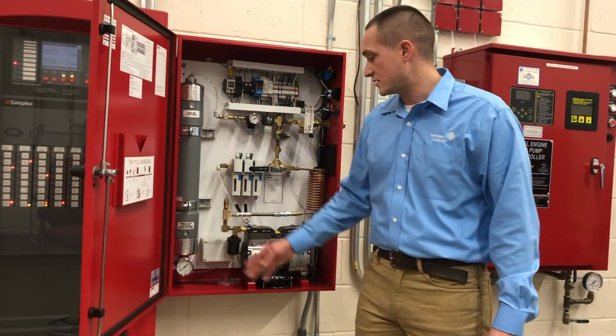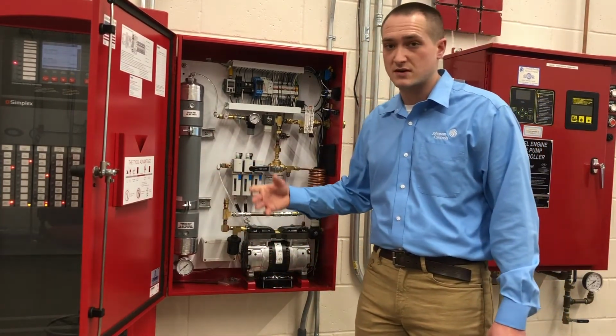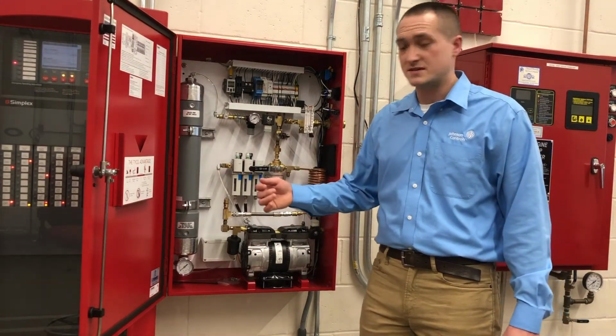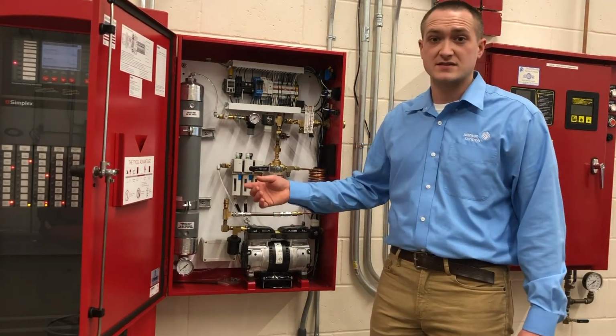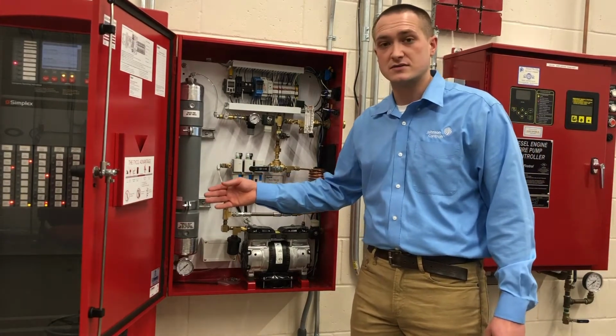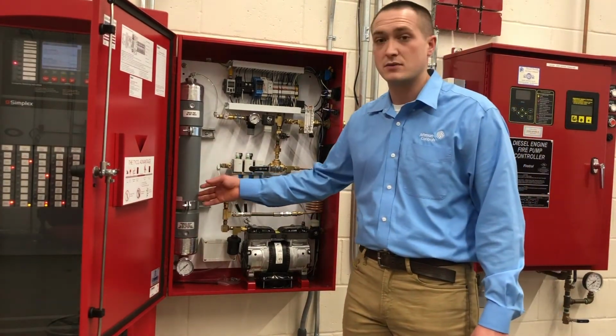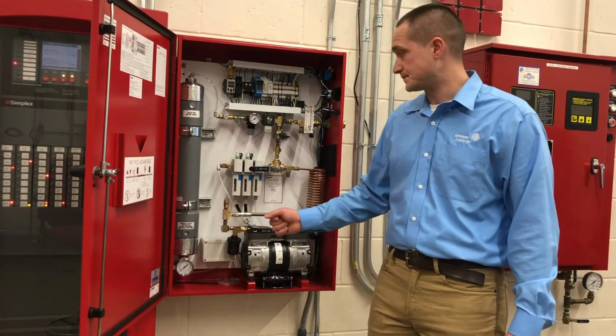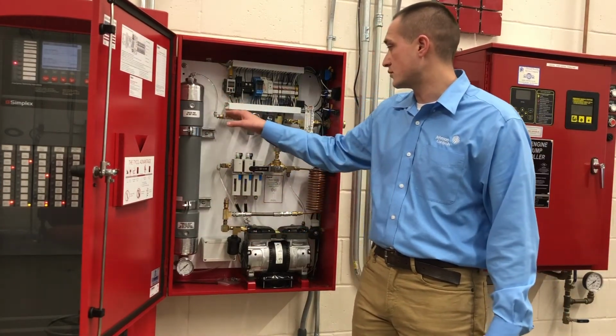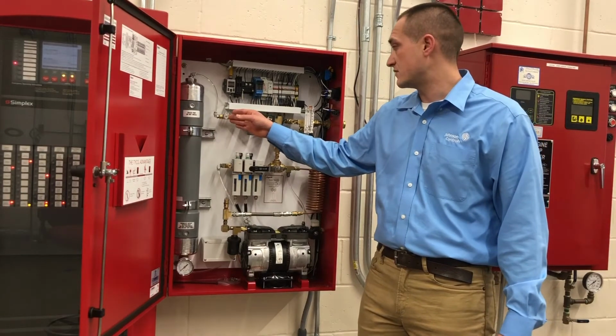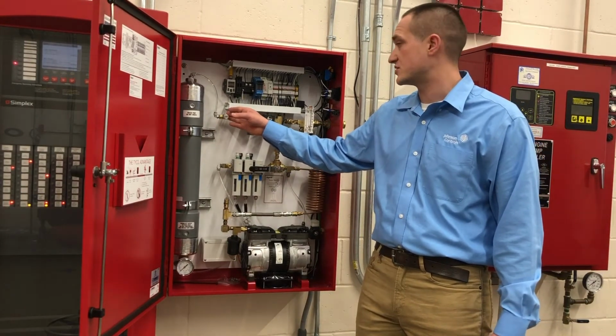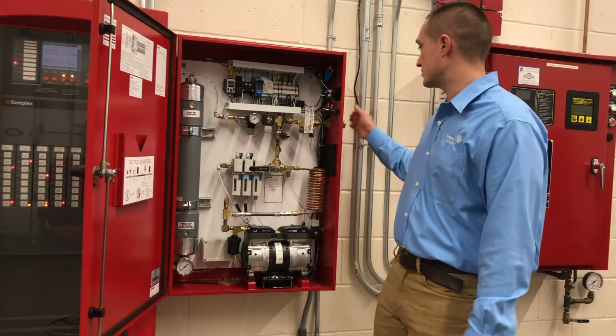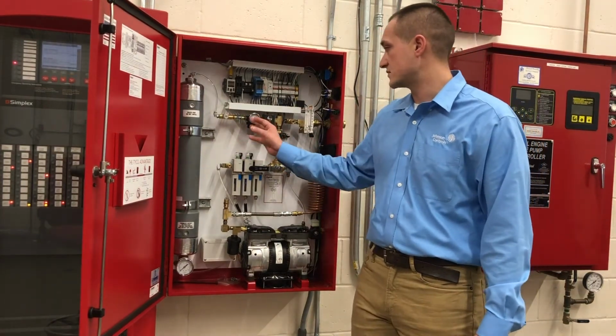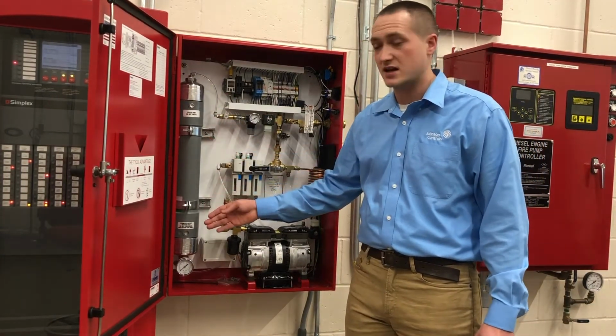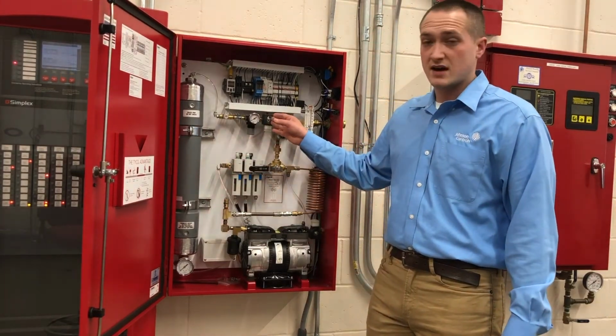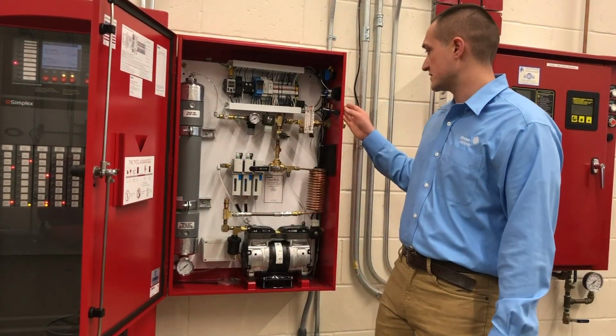This separation membrane is basically a series of small tubes, very small tubes, with orifices. Those orifices are sized in such a way that oxygen molecules can be purged off, but nitrogen will remain within the membrane. Nitrogen then comes up through a needle valve to slow the path of nitrogen. If we slow that path of nitrogen, we can ensure pure nitrogen into our sprinkler systems. Pressure regulator, so we trap a high pressure of nitrogen in here to purge that oxygen off. Solenoid valve separates the nitrogen unit from our sprinkler systems.